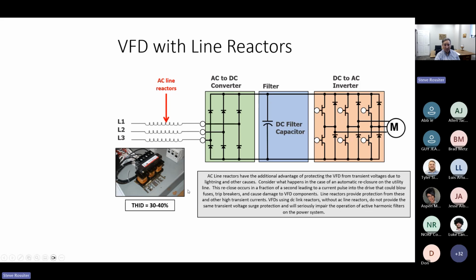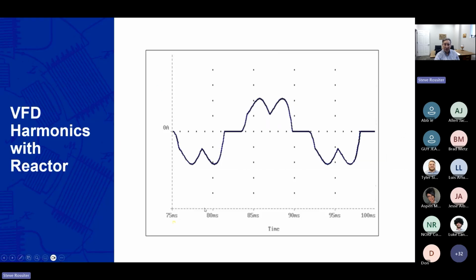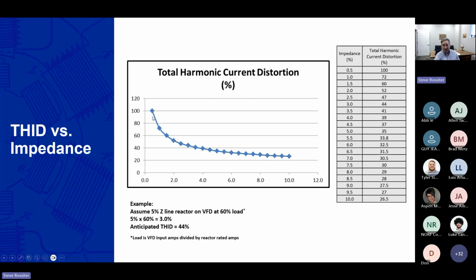And so, one of our engineers, who was the director of engineering at Geneva, said, I will put a 5% line reactor in front of every variable frequency drive that I ever buy. And that was his first practice. When you do that, you change that big double hump to a smaller hump. Now, it doesn't look elegant, but it looks more like a sine wave than not in this particular case. And here's a quick graph showing there are diminishing returns. You don't want to go up to a 12% impedance. 3% is a pretty good number. 5%, that's where you typically see reactors available in the commercial markets.